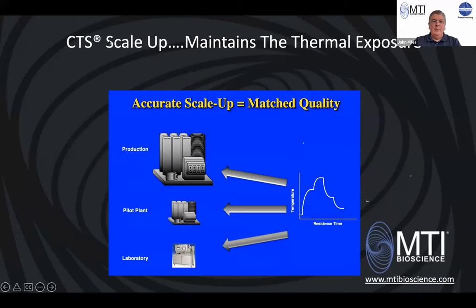Now, let's look at scale up. Continuous thermal sterilization, as well as HTST for viral inactivation, always maintains the same thermal exposure. So for example, if you have a smaller system in the laboratory, it's built and it has a specific time, temperature, history, or thermal exposure. When we go to the pilot plant, we can build another system that does exactly the same thing. And when we go to larger production scale, the same thing is true there. So that way you can maintain your quality because you've maintained the same thermal exposure.